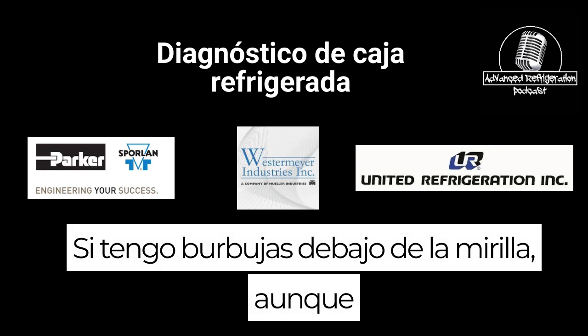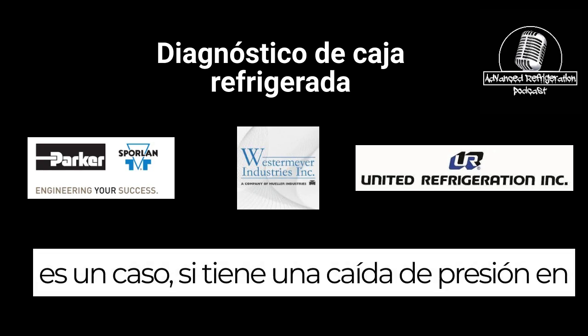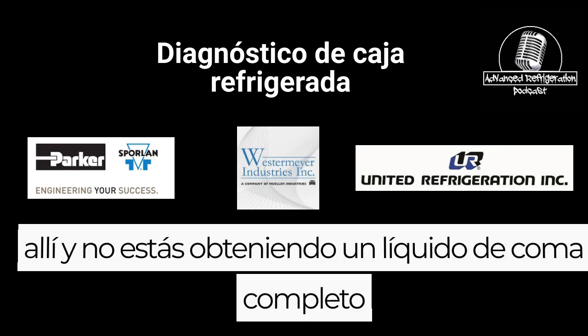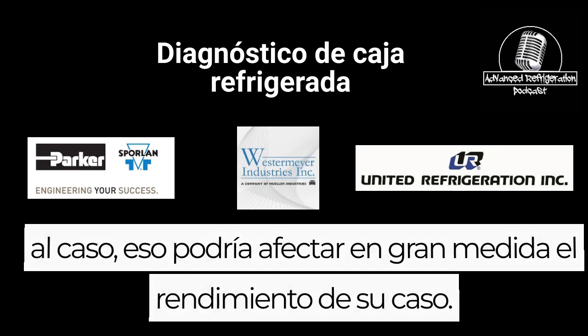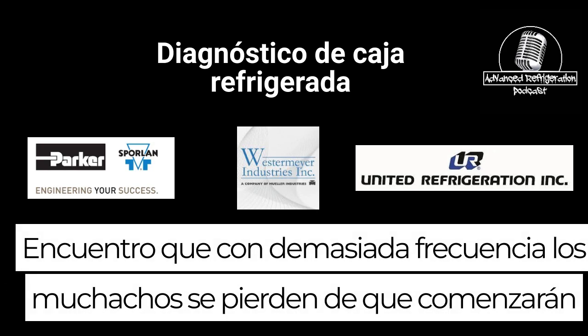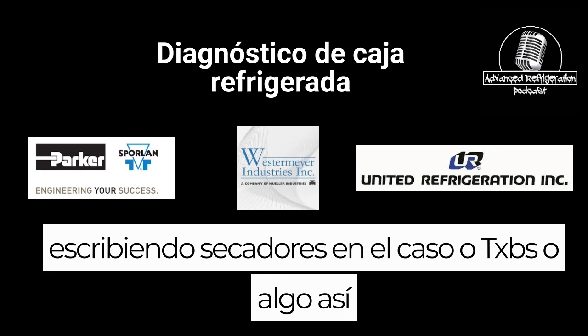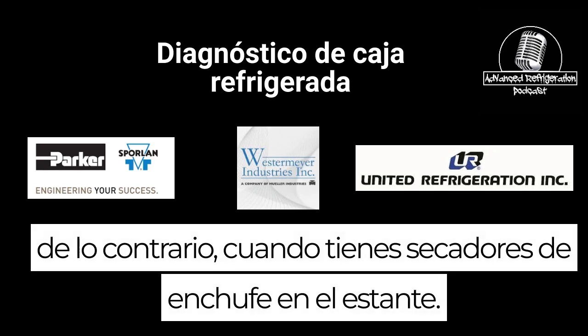I'll throw that on there, and then as I'm going through, I make sure my liquid levels look good, I'll graph them out if I can, and make sure my sight glass is clear at the liquid shell dryers. If I've got bubbles under the sight glass, even though it's one case, if you have a pressure drop on there and you're not getting a full column of liquid out to the case, that could greatly affect your case performance. I find all too often guys miss that. They'll start writing up dryers at the case or TXVs or something else when you've got plugged dryers at the rack.